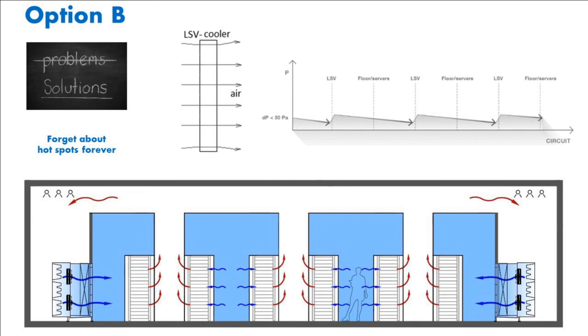The low-speed ventilation design provides for the operation of the server room and the coolers as a whole. Therefore, there are no bottlenecks or weaknesses. The large cross-section of the coolers gives a low and uniform air flow rate along the entire path with a resistance of less than 30 Pascal, which creates conditions for the absence of pressure drops that could lead to the appearance of the Venturi effect and overheating zones. On the other hand, it is an opportunity to work without overpressure, to drastically reduce the power of fans and their heat dissipation. In all existing low-speed ventilation data centers, service staff are not aware of problems with overheating zones.